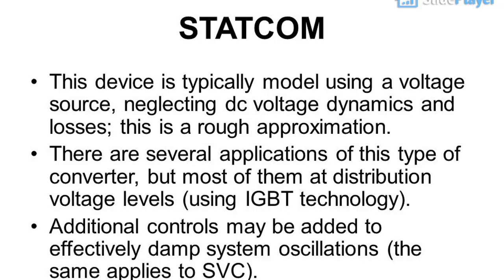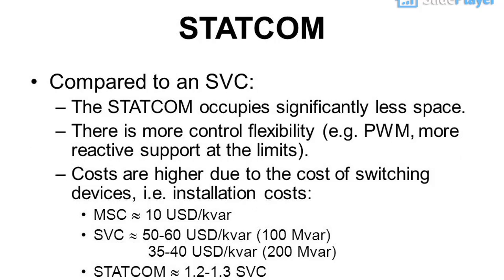There are several applications of this type of converter, but most of them are at distribution voltage levels using IGBT technology. Additional controls may be added to effectively damp system oscillations; the same applies to SVC. Compared to an SVC, the STATCOM occupies significantly less space and there is more control flexibility, for example PWM, and more reactive support at the limits.